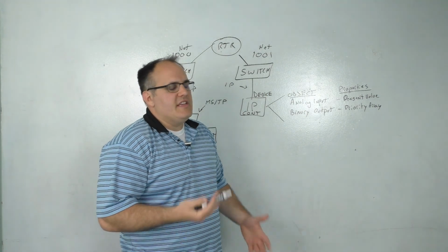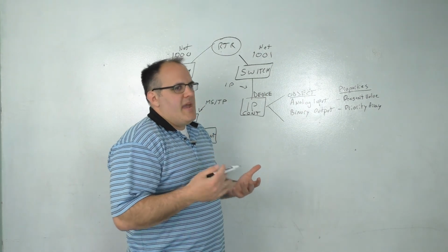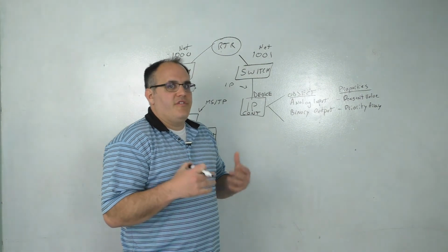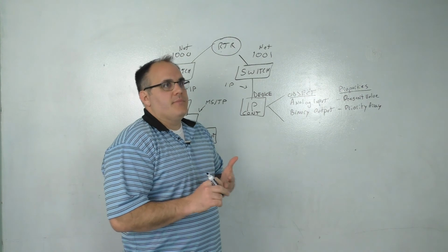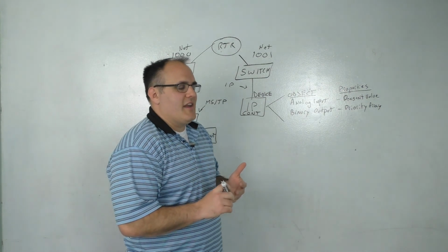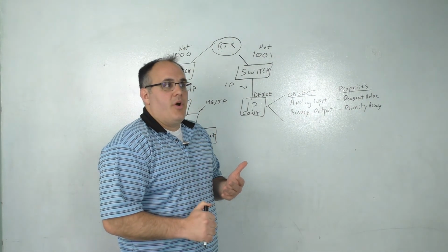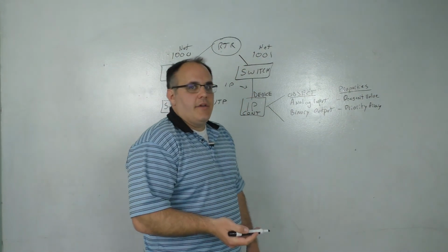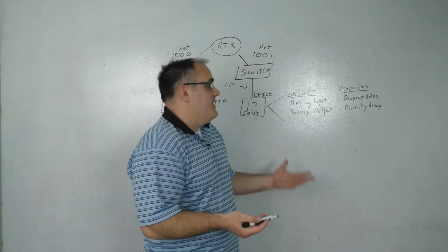and these devices having objects, there's 54 objects in BACnet, but out of all of those, you only need to know about a dozen, maybe a dozen and a half, maybe 18. But you don't have to know all 54. Some of those are file access or life safety, access control. I was saying file access. That's actually a service category. And some of them are things that you most likely are never going to use. But the big ones: analog, binary, multi-state values, schedule object, trend object, device object, event objects, things like that.